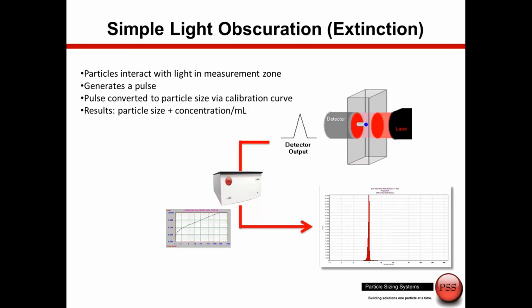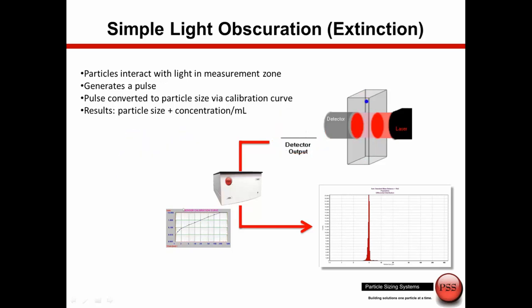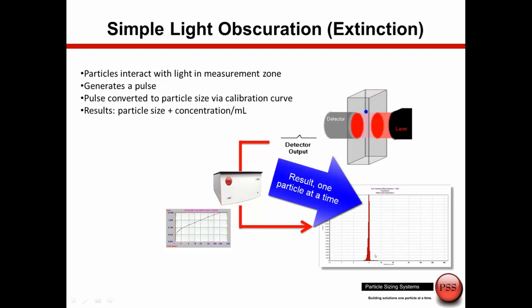The basic technology is simple light obscuration, or extinction. As particles pass through the cell, there's a light source and the particles obscure part of it, essentially casting a shadow. This generates a pulse which goes through a pulse analyzer, which we also call the counter. Through the use of a calibration curve, each pulse is converted into a particle size distribution.